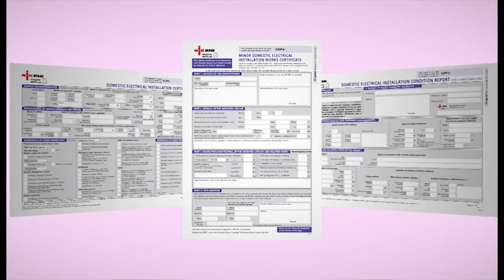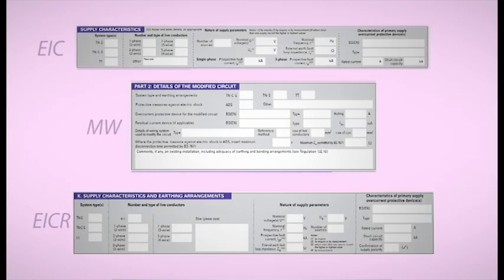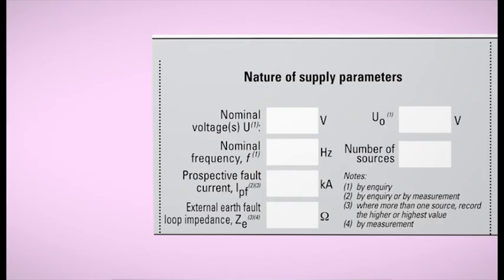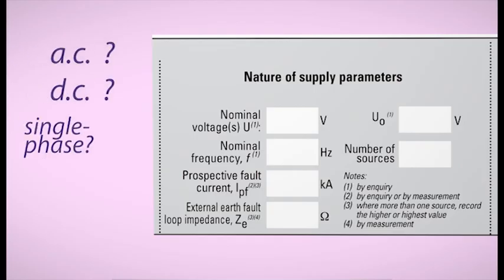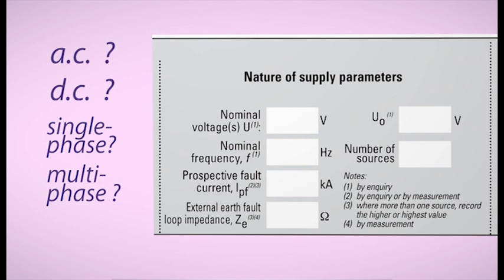Supply characteristics is relevant to all three forms, but more information is required to be filled in on the electrical installation certificate and the electrical installation condition report. One of the things that can be a bit misleading here is that the boxes for supply nominal voltage are blank, which has often invited the recording of the actual measured voltage. The reason why it's blank is that there are many variables for a circuit or installation. The supply could be AC or DC, single or multi-phase. It could even be ELV. So whatever you're working on, these values must be recorded.